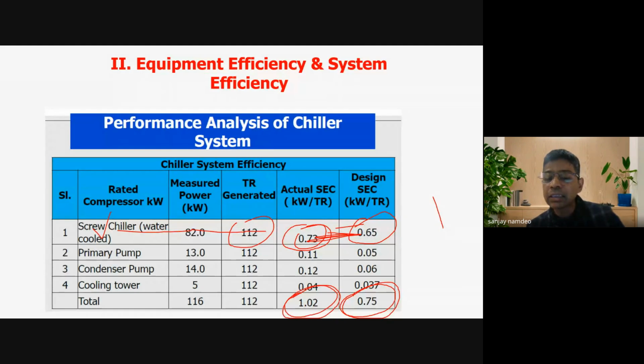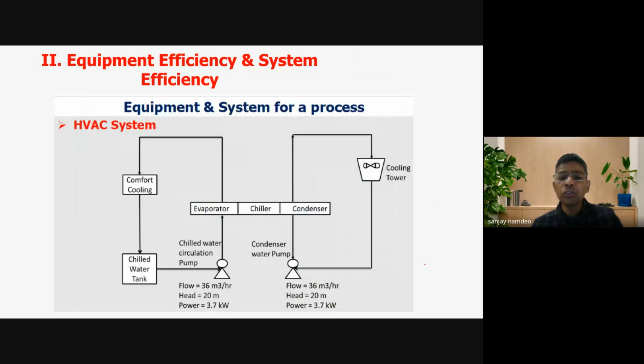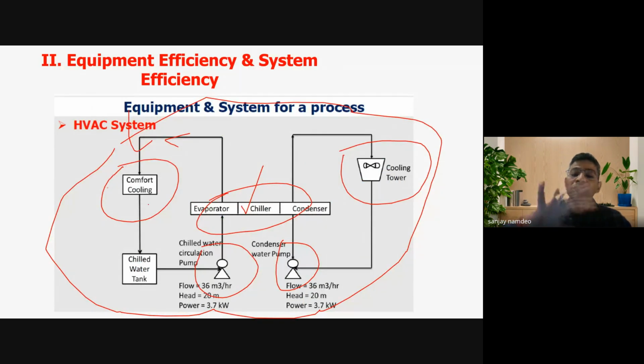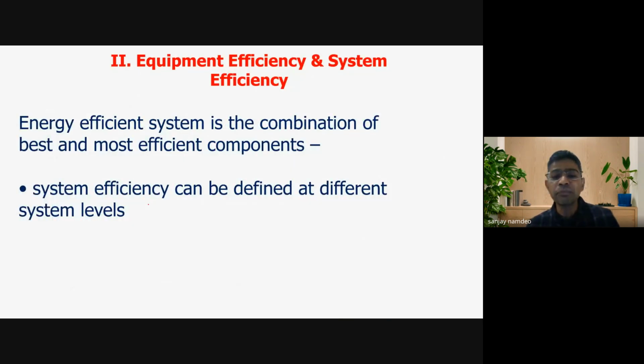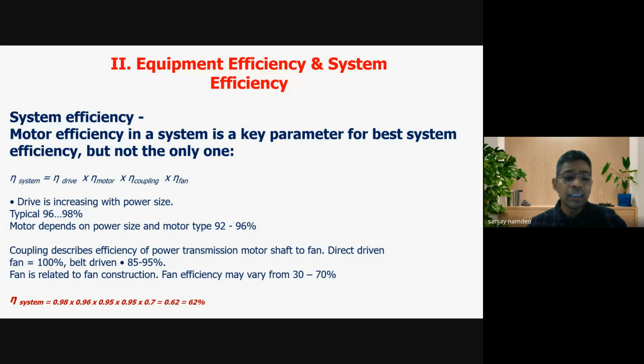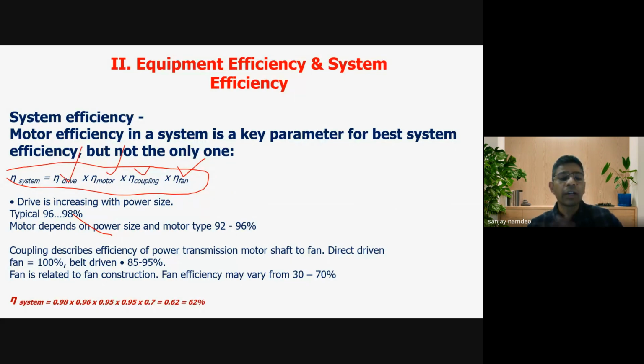When I'm just looking at the chiller equipment, I can still say that the actual is close to design, right? But when I compare the system efficiency, I come to know the actual picture: my system efficiency is much lower than the design system efficiency. So we should consider the efficiency of the entire system, not only one equipment. So what is the rule of the system efficiency? Let us say my system is a fan coupled with a motor, and the motor has a starter or drive. So my system is all these four equipment.